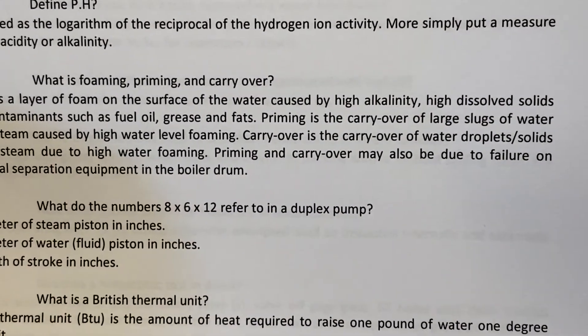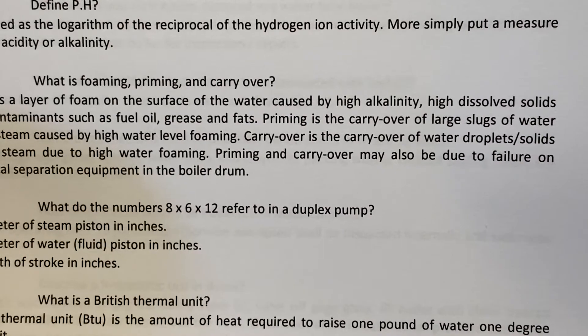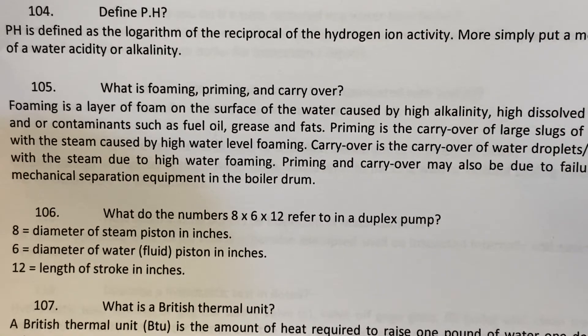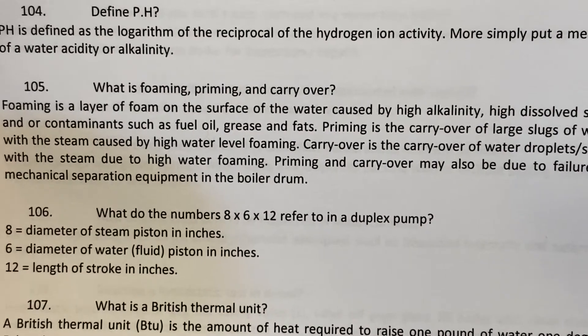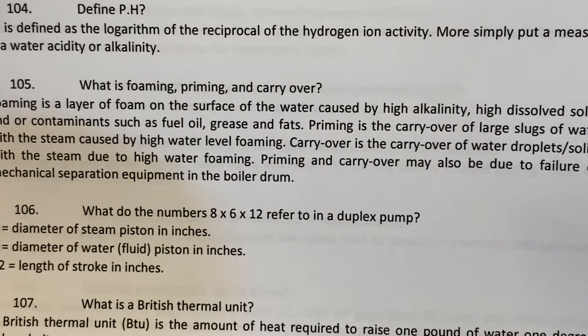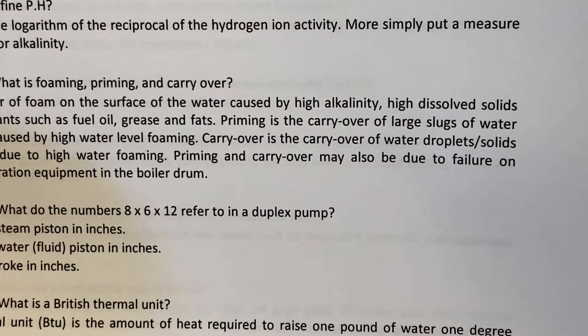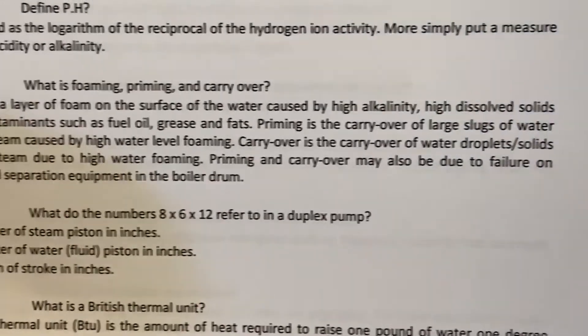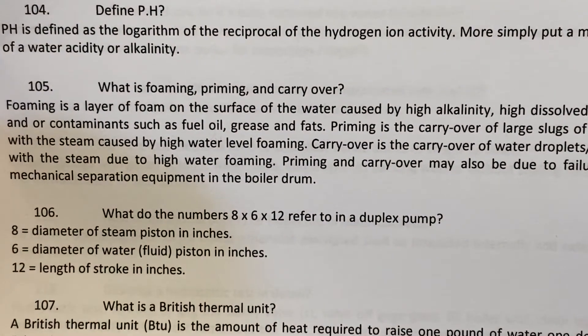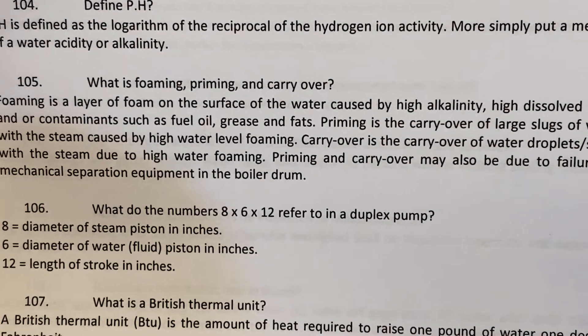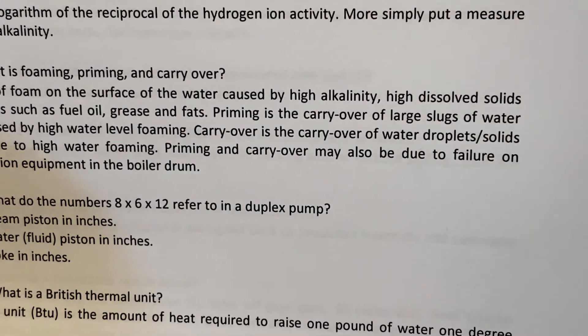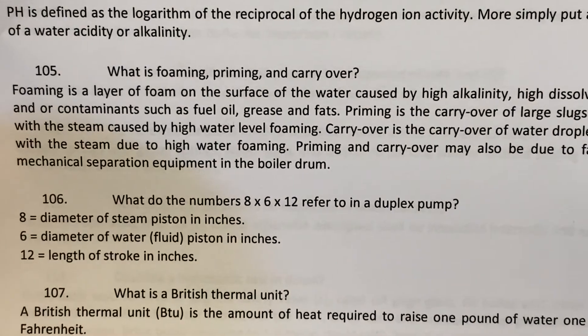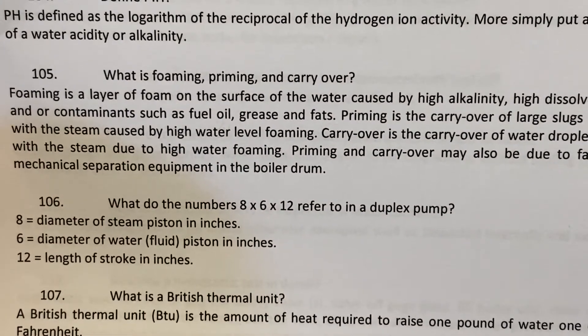What is priming and what is carryover? Priming is the carryover of large slugs of water with the steam, caused by high water level or foaming. Carryover is the carryover of water droplets and solids with the steam due to high water level or foaming. Priming and carryover may also be due to the failure of mechanical separation equipment in the boiler drum.